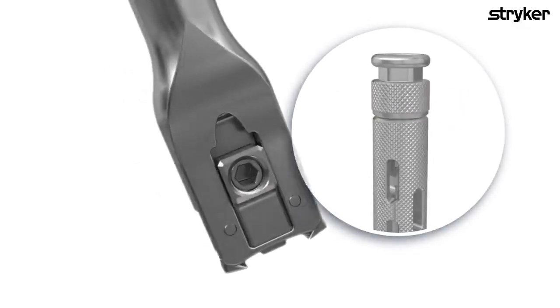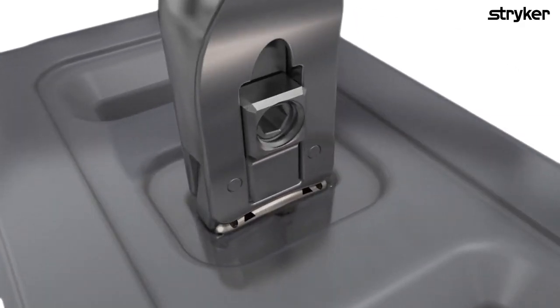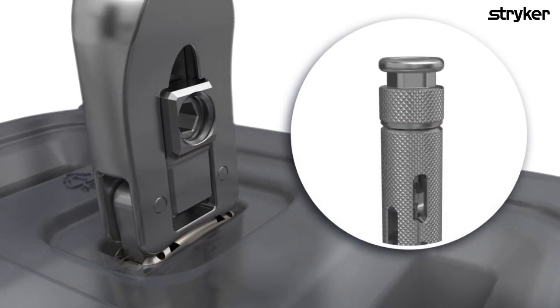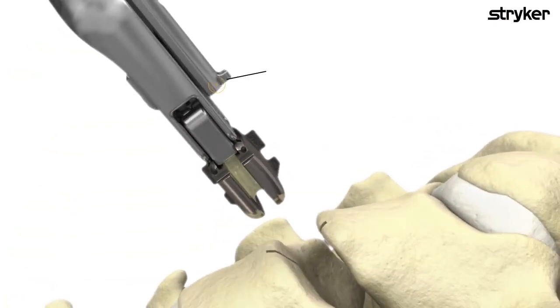Position the distal end of the inserter to the anterior side of the disc. Indicators on the disc aid in determining correct orientation during loading and implantation. Rotate the proximal knob of the inserter in a clockwise direction to close the grips and secure the disc to the inserter.